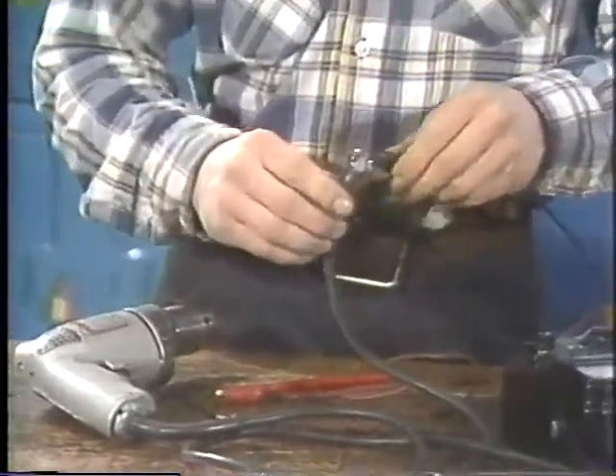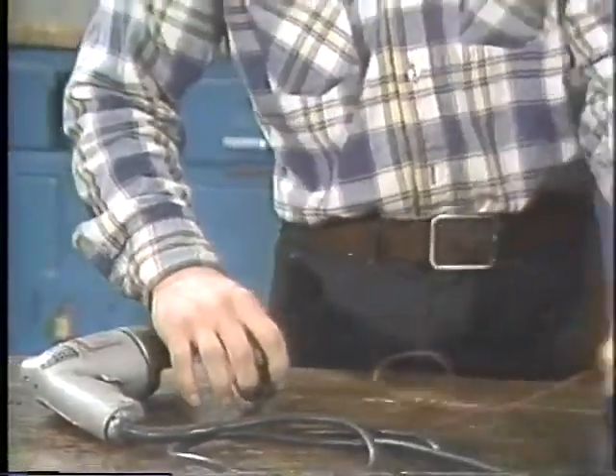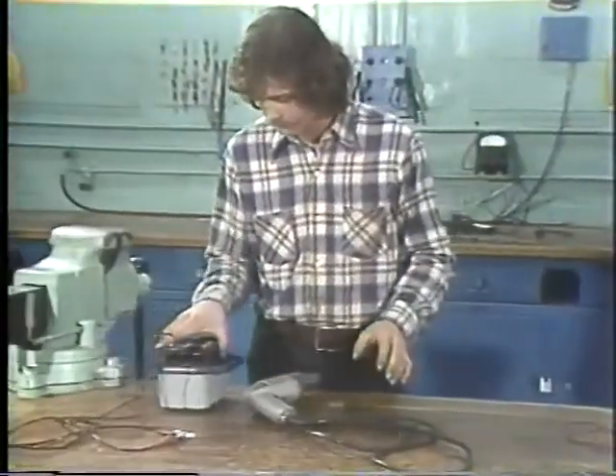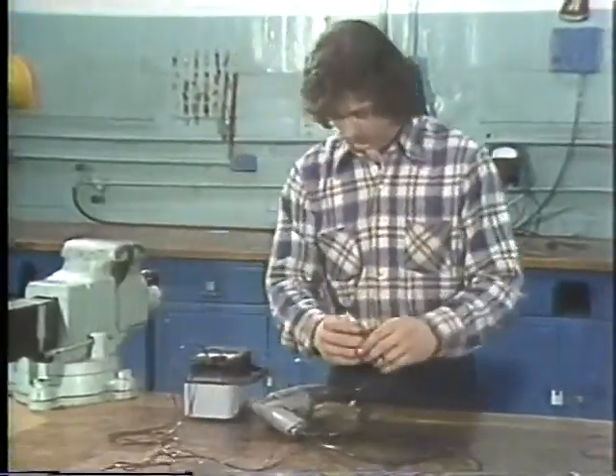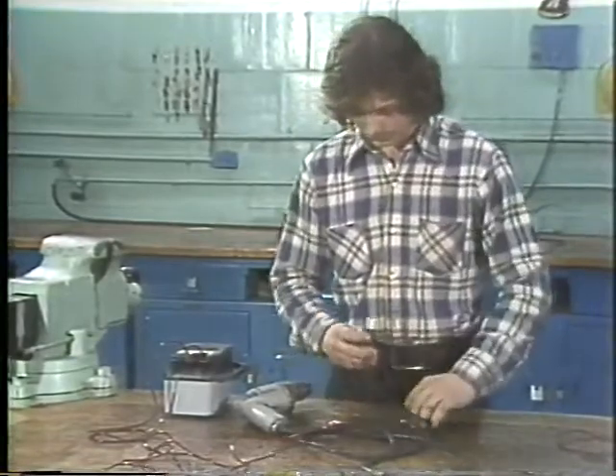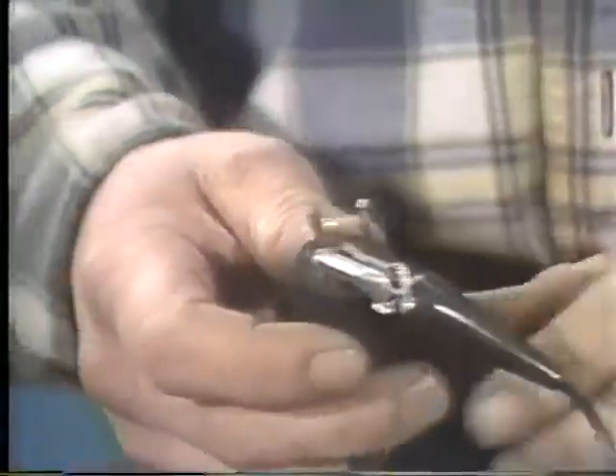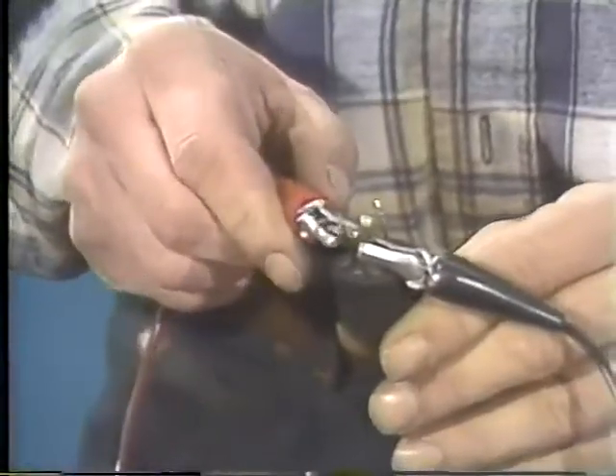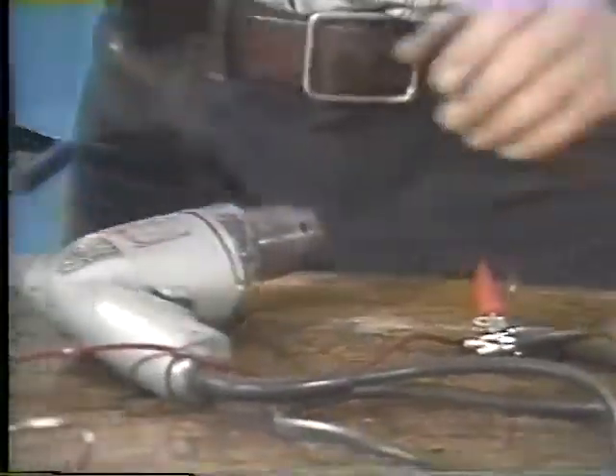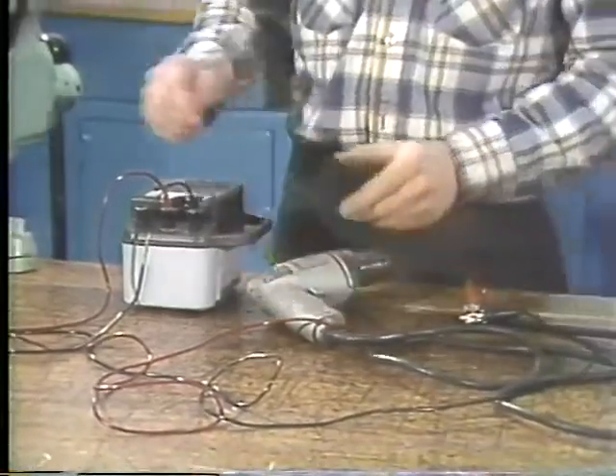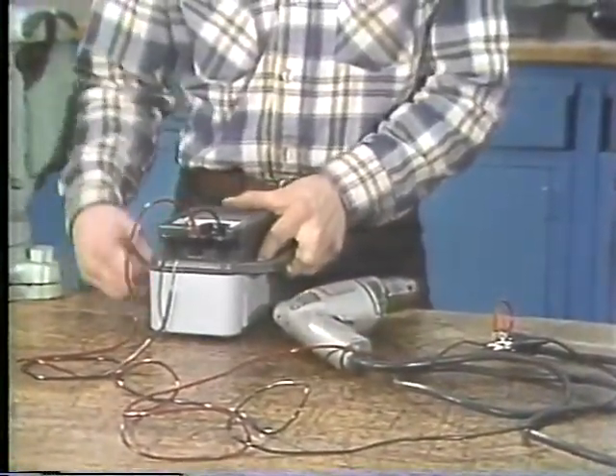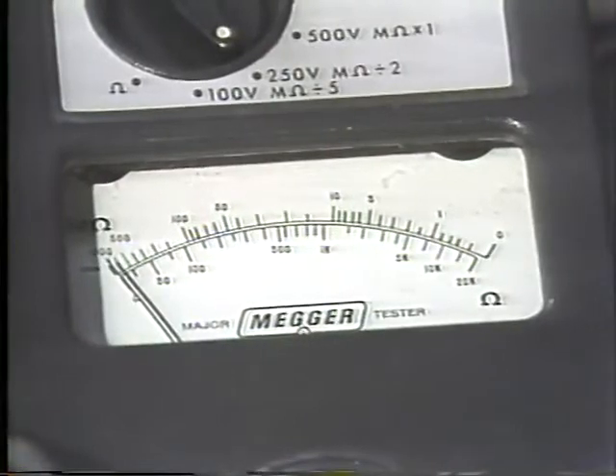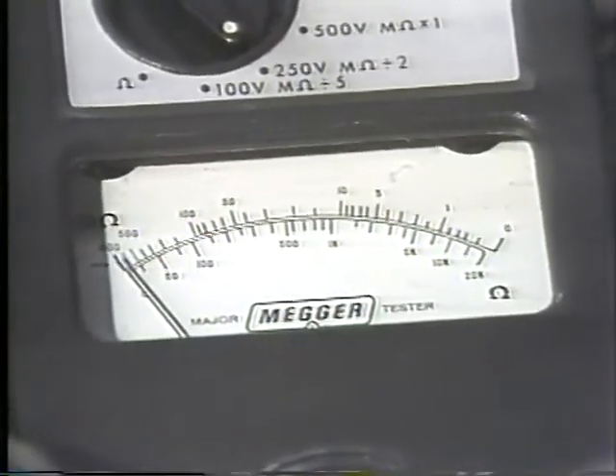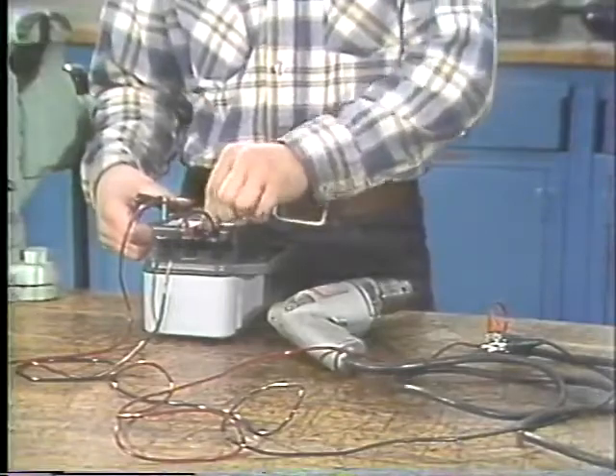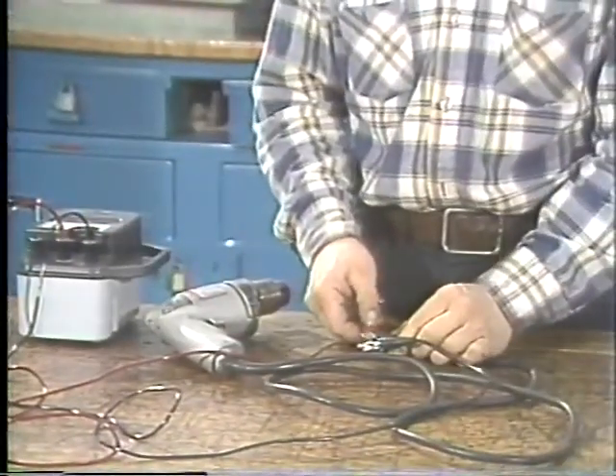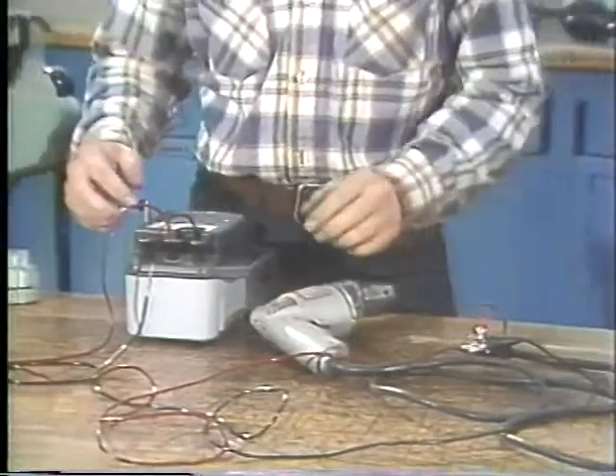Now that he knows that the drill casing has a good ground, his next test is to see if there are any faults between the line conductors and the casing. He'll make a resistance measurement with a megohm meter. A low resistance reading between the ground conductor and a line conductor would indicate a fault. To make sure the test checks all the circuits in the drill, he locks the switch in the on position. The resistance is near infinity. No sign of a fault here. To double-check the test, though, he'll repeat it after switching a probe to the other line conductor.